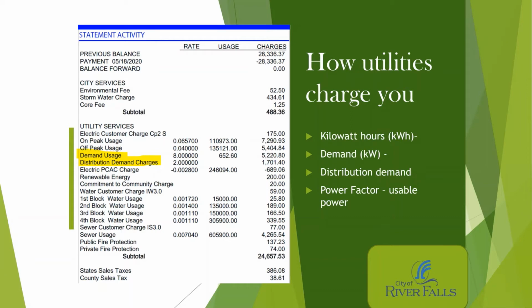If you're able to control that demand and reduce it, you're not only going to save that month, but you'll save for months on end. Some of these spikes come from fire flow pump testing and the time of day they're used. So the distribution demand charge is a smaller charge, but you will pay for it—and we've seen some of our larger customers pay for mistakes made 11 months ago.